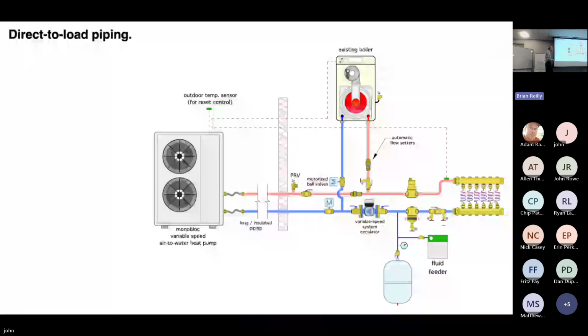What's controlling those valves in that sense? Whatever is calling the heat pump to operate, whatever contact closure you're using to call the heat pump to operate, you could control those valves. Correct. So this has to be open if this is on, this has to open if that is on. And it depends on the valve too. You can get motorized valves that are motor open, spring close, so you give them power and they open, remove power and they close. Other valves power open and also power close. So depending on what the valve electrical requirement is, you might have to use a relay or something, but the bottom line from a control design standpoint is that if that's on, that valve's got to be open.